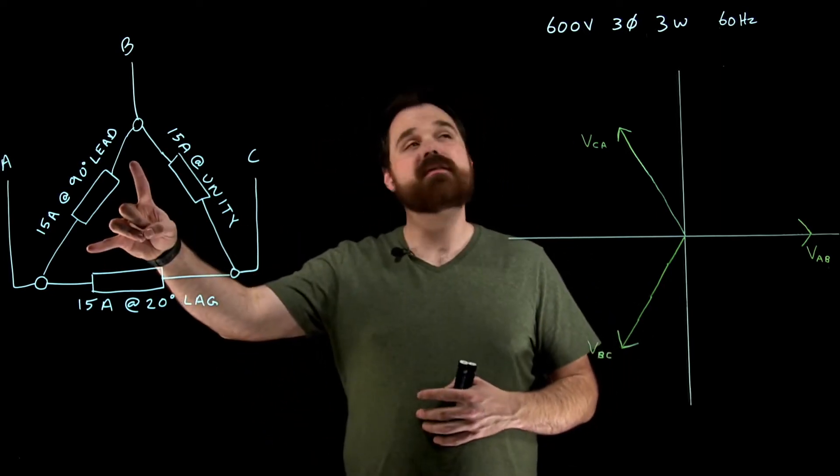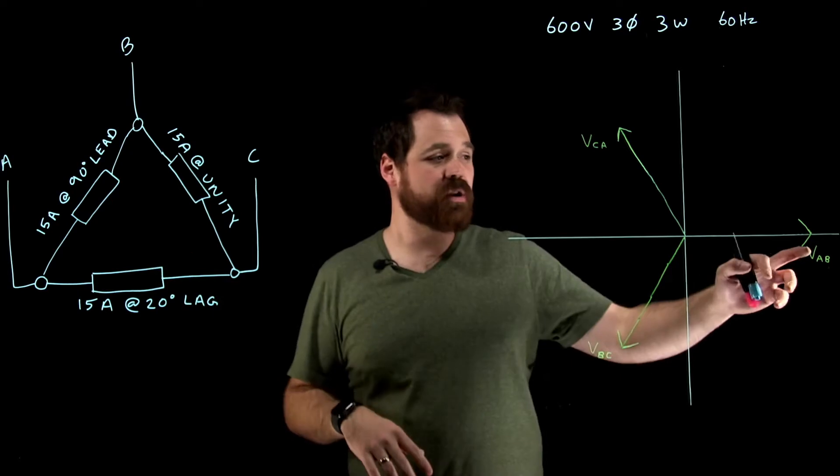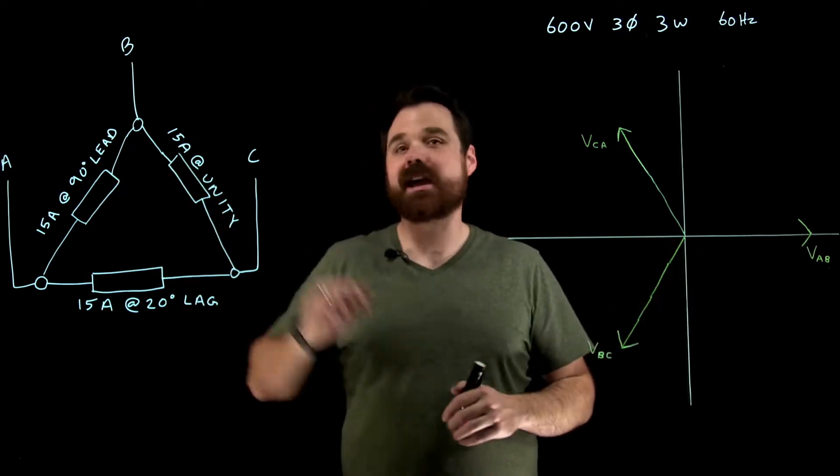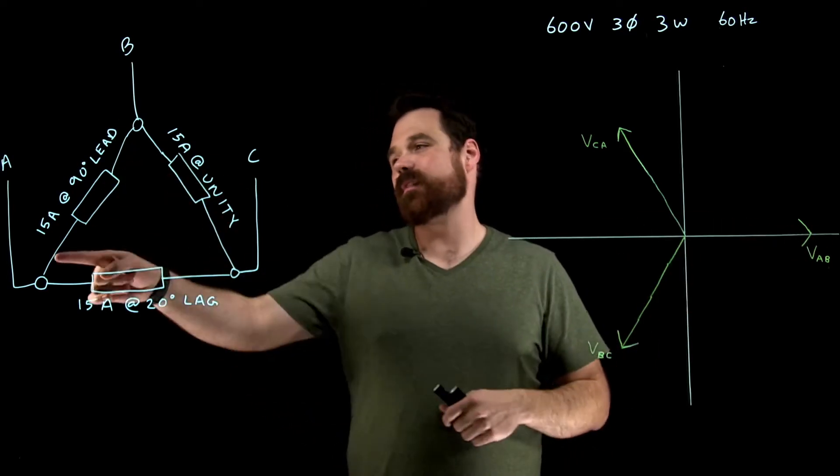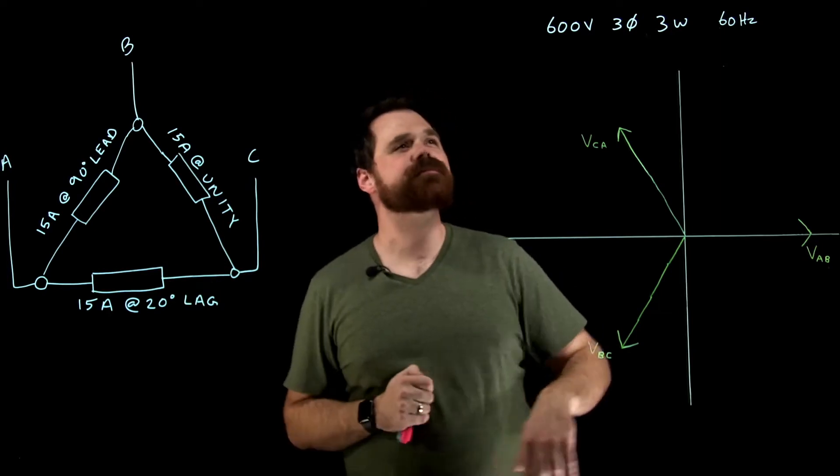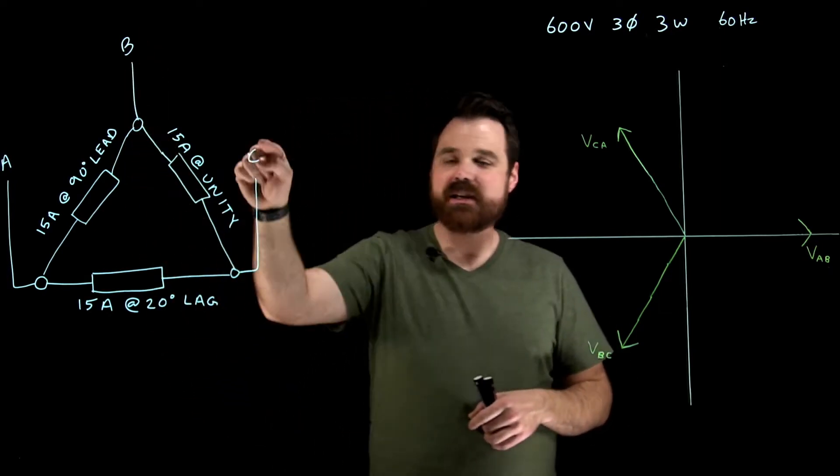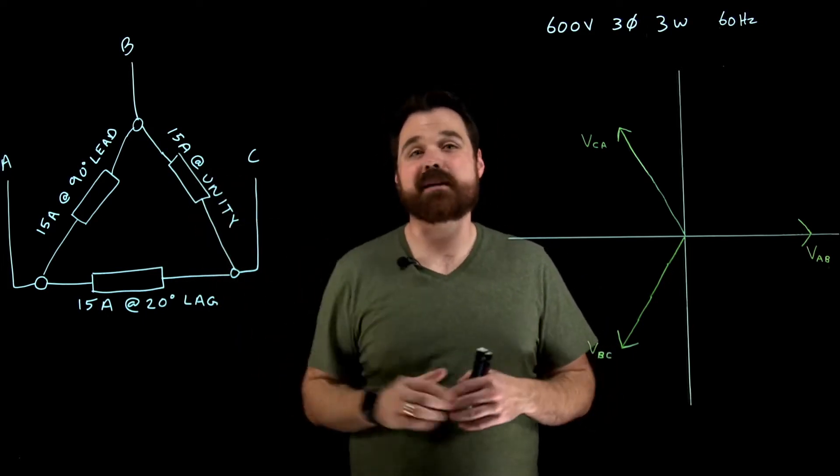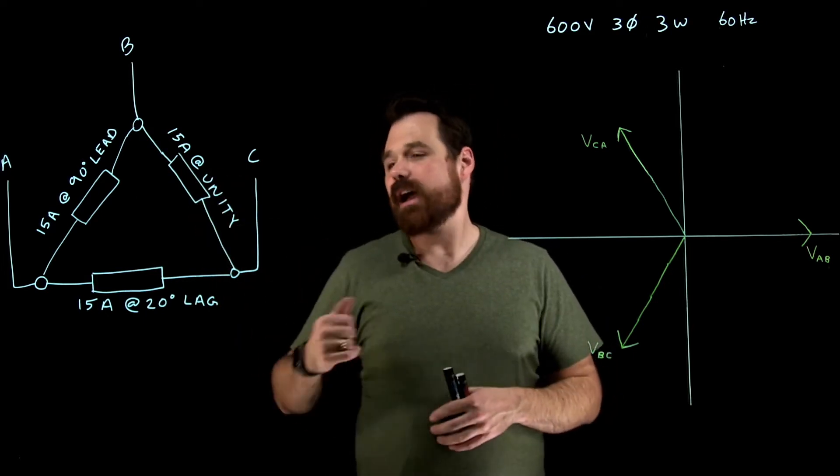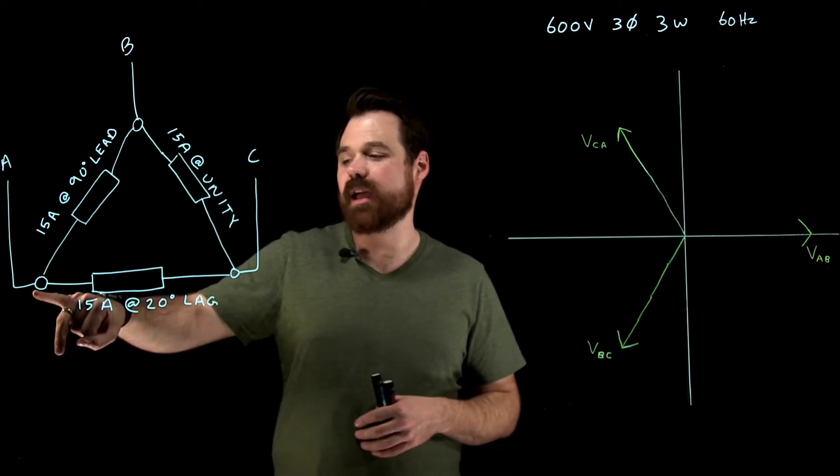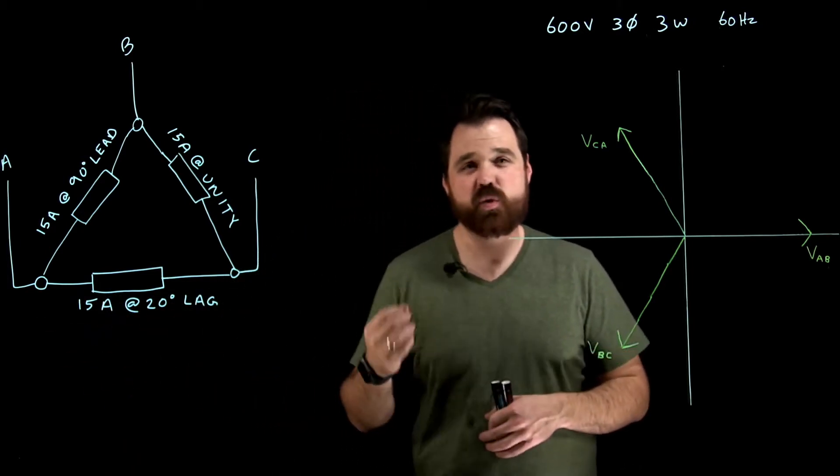So here, in phase A, which would be with my V A to B right there, I see 15 amps at a 90 degree lead. In phase B, which goes from B to C, I see 15 amps at a unity power factor. And then from C to A, I see 15 amps with a 20 degree lag.